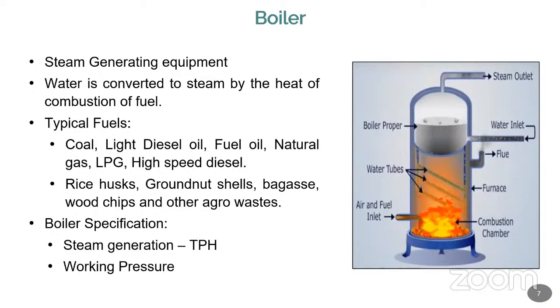Then, similar to the compressor, the capacity is TPH, but also the working pressure. At what pressure are you developing the steam? Because you are supposed to send the steam to the process, but the process may be some distance away from your boiler. Normally the boiler is in one place and the process is in another place. So you need to transmit the steam with the help of a piping system, and you require a force.